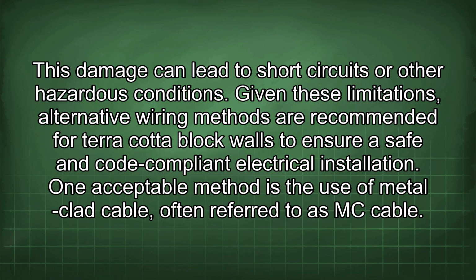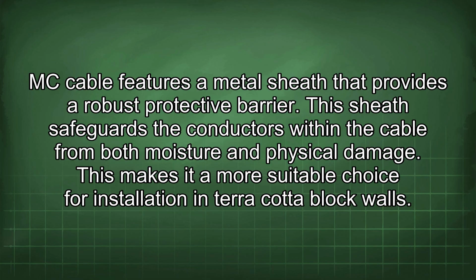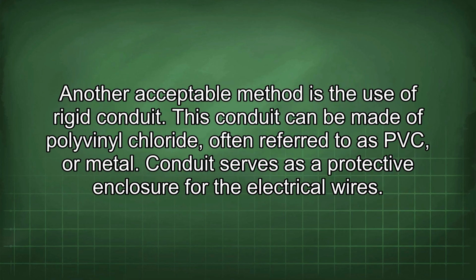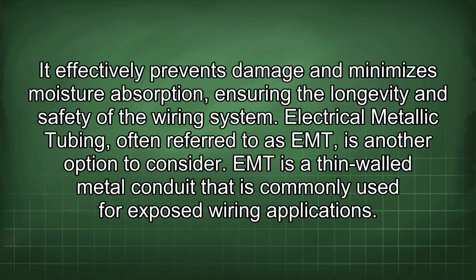One acceptable method is the use of metal-clad cable, often referred to as MC cable. MC cable features a metal sheath that provides a robust protective barrier. This sheath safeguards the conductors within the cable from both moisture and physical damage. This makes it a more suitable choice for installation in terracotta block walls. Another acceptable method is the use of rigid conduit. This conduit can be made of polyvinyl chloride, often referred to as PVC, or metal. Conduit serves as a protective enclosure for the electrical wires. It effectively prevents damage and minimizes moisture absorption, ensuring the longevity and safety of the wiring system.